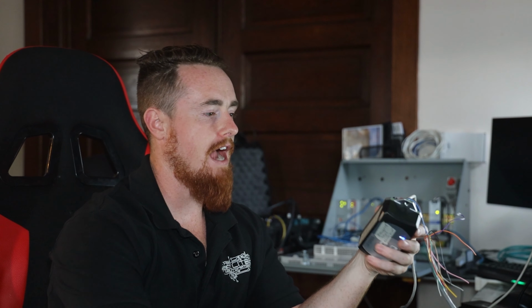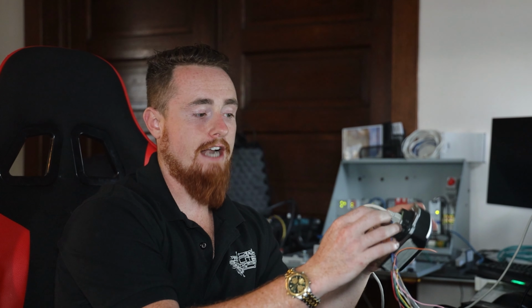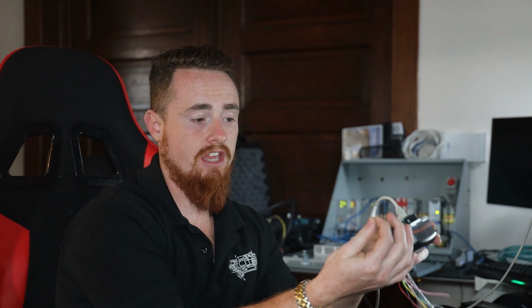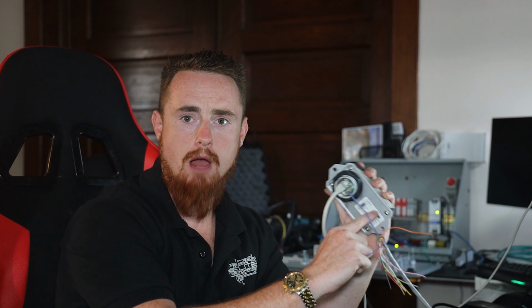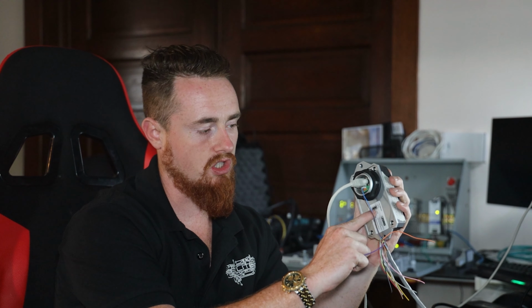I'm not going to do a factory reset just because I don't feel like dealing with it right now, but in order to do a factory reset, remove power, then apply this 24 volt signal to the back right here. There'll be a factory reset terminal, and there's also a diagram right here on the back. All of these come with a diagram that tells you the 24 volts, the 0 volts, and the factory reset terminal.